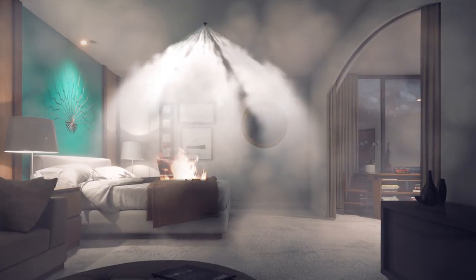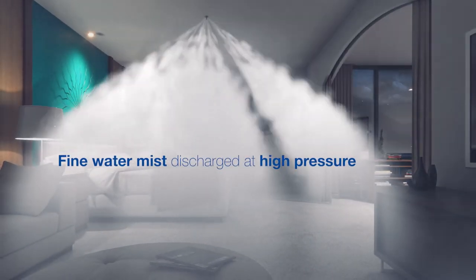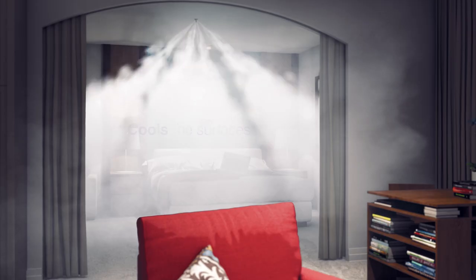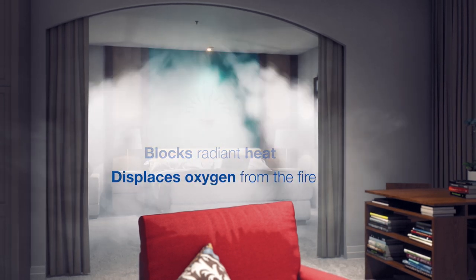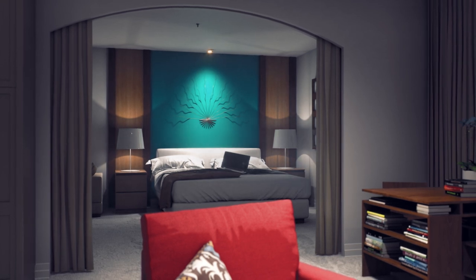Extremely fine water mist discharged at high velocity effectively cools the surfaces and blocks radiant heat, preventing fire from spreading. At the same time, water mist is vaporized by the heat, which displaces oxygen from the fire to quickly suppress the flames.